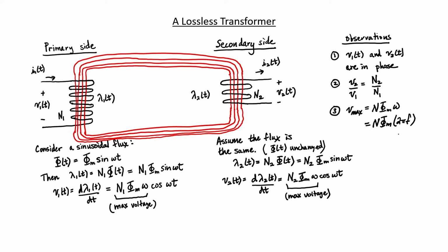Because of this concept of magnetic permeability, it's difficult for some materials to have a huge field concentration within them. In other words, there's usually a maximum phi that a particular material can handle well. From this expression, we can see that the maximum voltage is related not only to the turns ratio, or the number of turns, but also to the frequency. If we want to hold the voltage constant, then as the frequency gets lower and lower, we're going to need more turns on the transformer to accommodate it. This means that transformers designed for use at high frequencies will have fewer turns than transformers designed to operate at low frequencies.